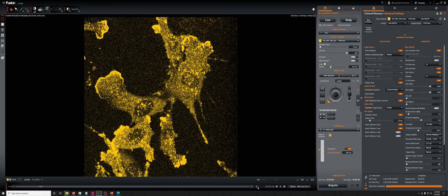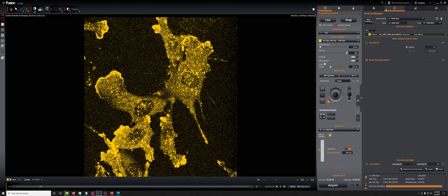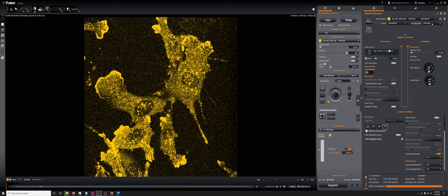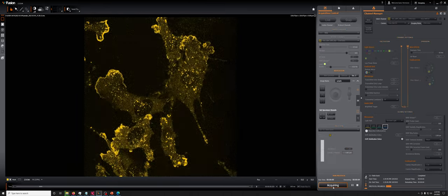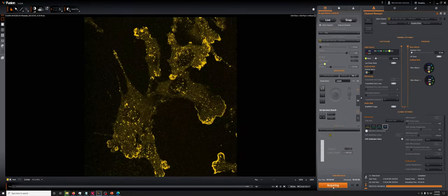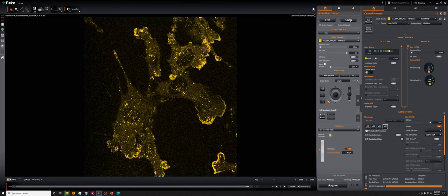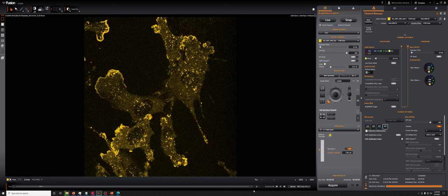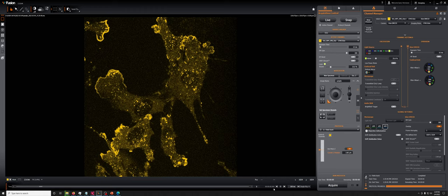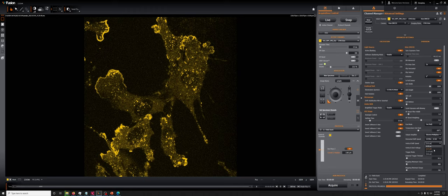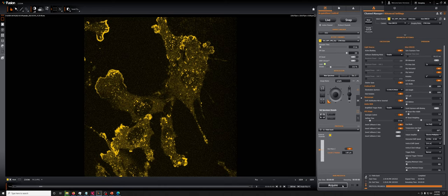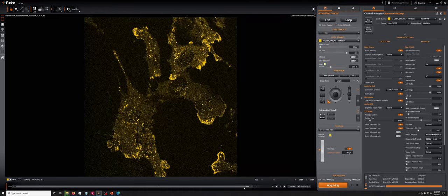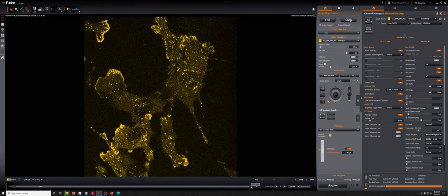Let's go back here and just hit acquire. This is 1024 by 1024. And you can see that between the first and the second frame, we had a 10 millisecond exposure, but it took 42 milliseconds before we did the second one. So there was an extra 32 milliseconds. If I drop this to 0.6 and I increase the vertical clock voltage to plus one, and I try the same thing, you'll see that that number will be smaller. And indeed, you can see that it went from 42 to 39.